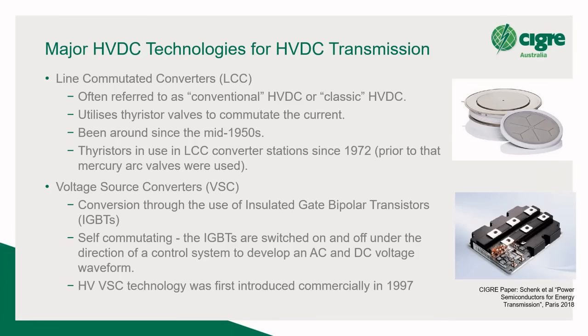Okay, sorry about that. So VSC technology is a new kid on the block. It was first introduced commercially in 1997. Originally, it was considered as a technology suitable for small power application. And at the time in the late 90s, HVDC was only associated with large power, long distance power transmission. And that's pretty much driven by the overall cost and magnitude of LCC technology at the time. But over time, people started realizing there are actually some unique applications for VSC, and it's actually been developing pretty fast. And right now, transmission levels of 1,000 megawatts, 2,000 megawatts are not only possible, but also under construction. Okay.